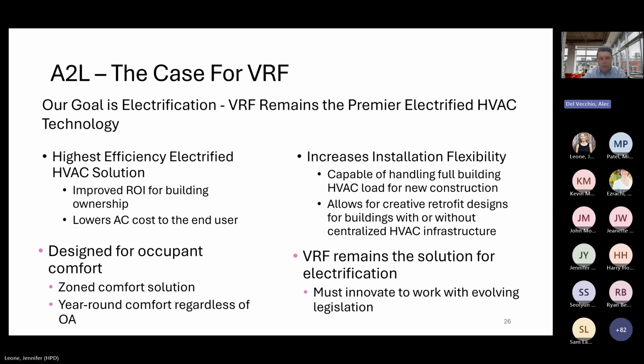We can provide a zone solution that allows us to decrease the overall size of the VRF systems so that we more closely align with these new A2L goals. That ties into increased installation flexibility. We can realistically design these systems in interesting ways to meet the goals, whether it's routing piping external to the building or going with smaller, local systems. We can creatively retrofit designs, especially where there's no existing centralized HVAC infrastructure. This has always been an advantage for VRF and continues to be so.